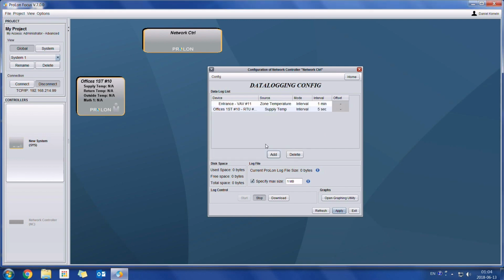I could add on the rooftop controller as well, and once again, we can choose which point we want to monitor, and maybe I want to monitor the supply temperature every 45 seconds or every 2 minutes, whatever we want it to be. All this information is stored on an SD card, which can be inserted onto the network controller. So it doesn't matter whether you have a 1 gigabyte SD card or a 2 gigabyte or a 4 gigabyte SD card.